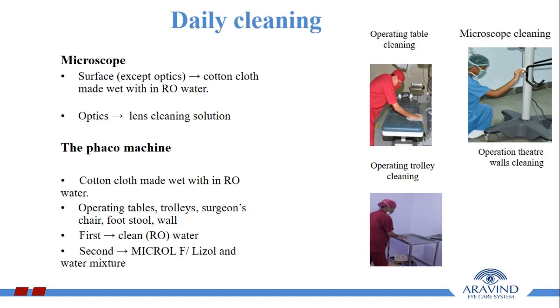Daily cleaning. Microscope: the surface except optics is cleaned with a clean cotton cloth made wet with RO water. Optics are cleaned using lens cleaning solution. The phaco machine is cleaned using a cotton cloth made wet with RO water.